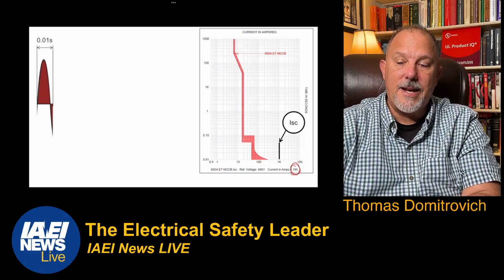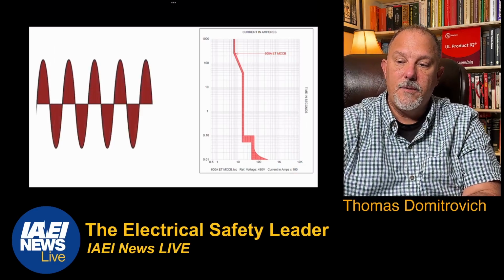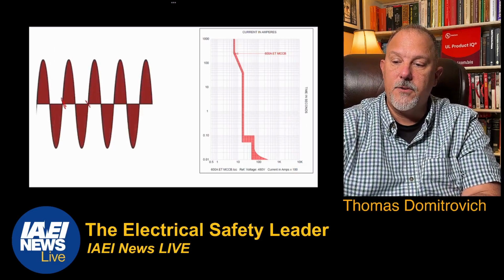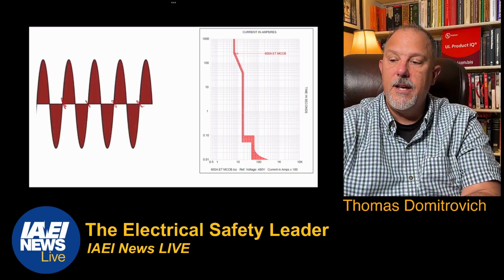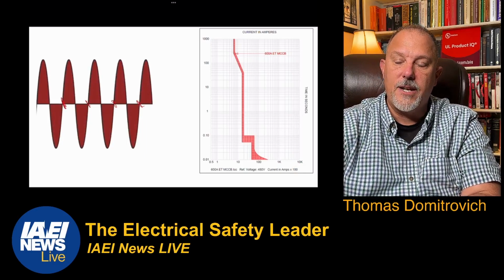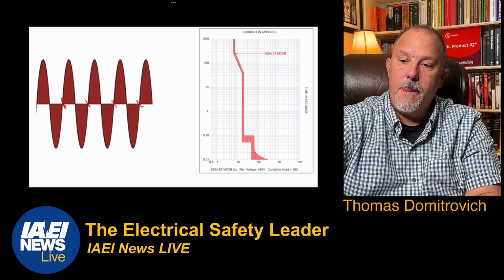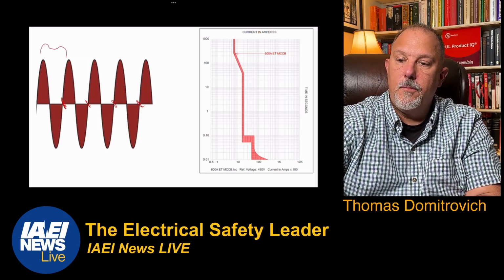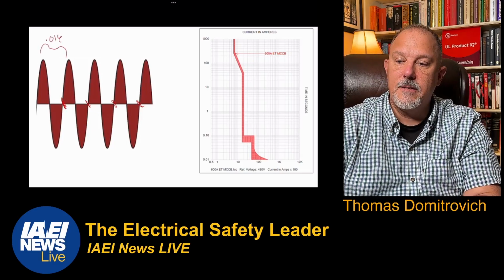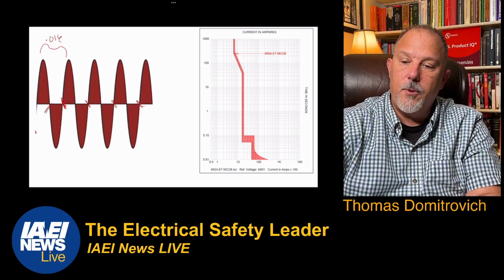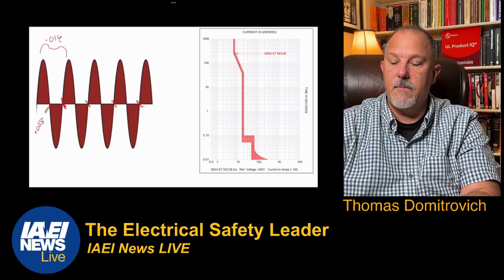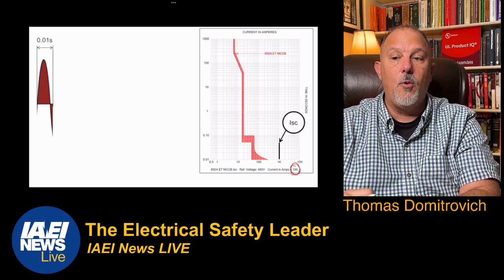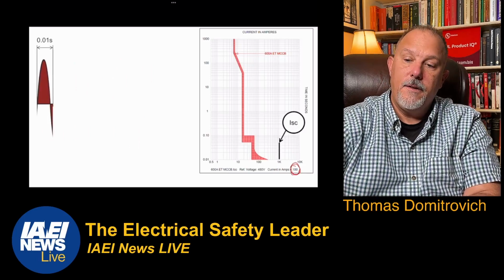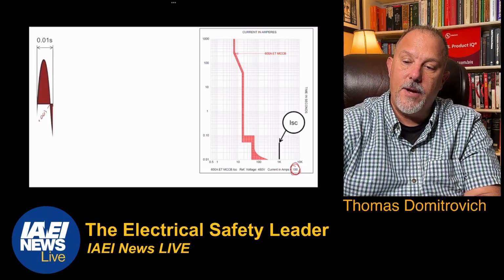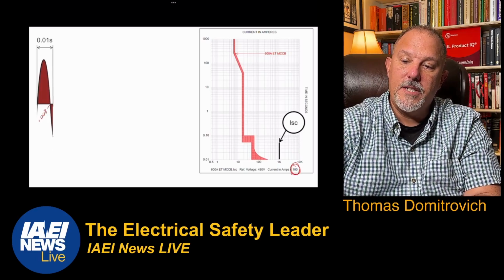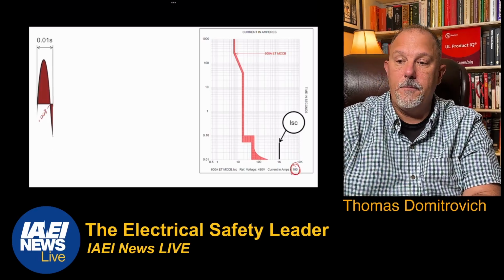So 0.01 seconds, if you look at this, remember that's 1 cycle, 2 cycles, 3 cycles, 4 cycles, 4.5 cycles here. If this is 1 cycle, this is 0.016. This is 0.008. So if I look at 0.01, if this is 0.008, that's about 0.01. That's what you're letting through.